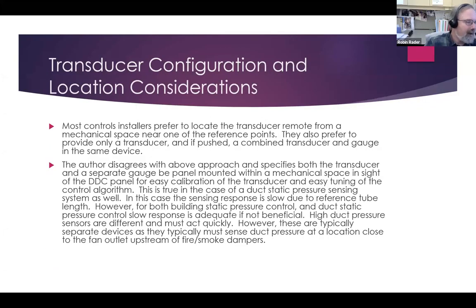I'm going to talk a little bit about transducer configurations and location considerations. I personally like to have the transducers back in the mechanical room in a panel with the gauge mounted on the panel door.